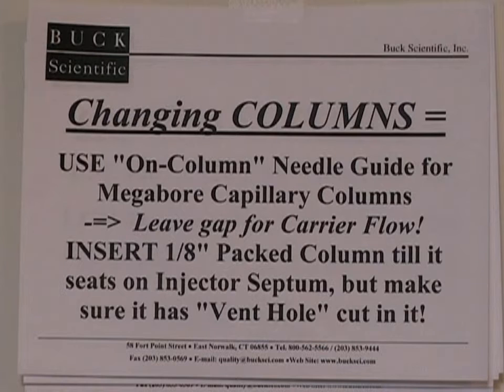Likewise, for a 1/8 inch packed column, make sure that there is a vent hole to allow the carrier gas to go through, or when you seat it up against the septum, you will not get any flow through the column. Check these if you ever have difficulties getting peaks off the system.